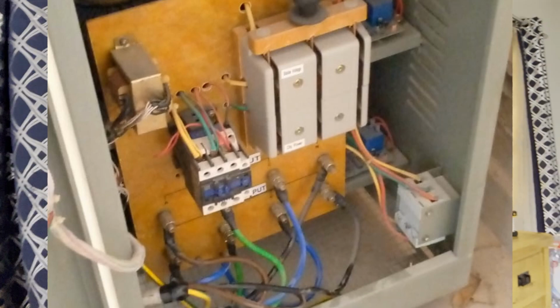Then I got them to turn on all the loads in the house: all the lighting, all 9 air conditioning units, the water pumps, and opened the taps so the automatic pumps were working. I wanted to test the system at maximum load. Obviously this is a house with no kitchen appliances yet, no fridge, no freezer, no electric cooker, so I just used the loads available to put the system to a test. In electrical terms, we call it a soak test.